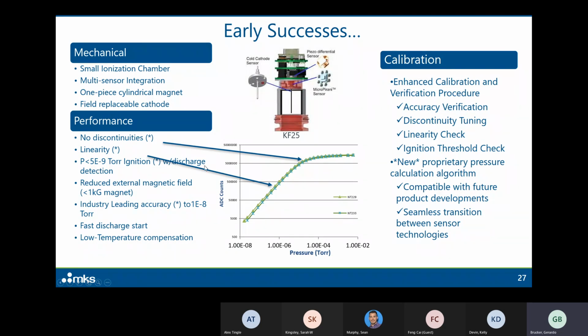In terms of performance, we were able to achieve no discontinuities and a very linear response. We were able to achieve ignition pressures lower than 5 to the minus 9 torr, which was a requirement for the 1 to the minus 8 minimum reportable pressure, which also allowed us to incorporate a first of its kind discharge detection mode, which is very important for you to know that things are going well. We were able to do this with a reduced external magnetic field, while at the same time providing, and this relied a lot on the enhanced calibration procedure, industry-leading accuracy, a very fast discharge start, and we even threw in a low temperature pressure measurement compensation algorithm into the mix.